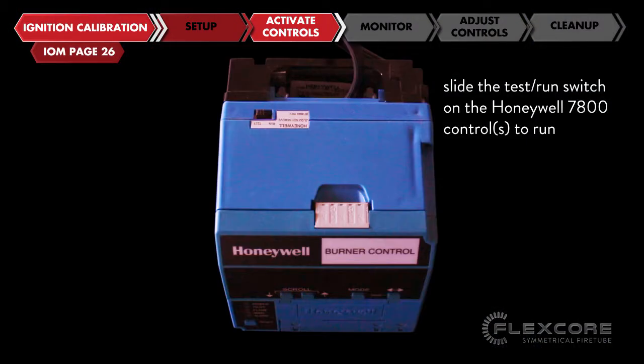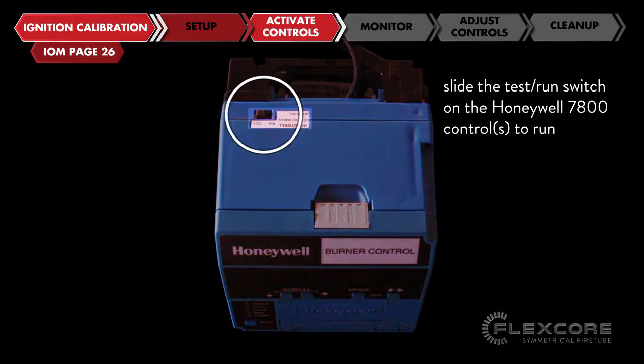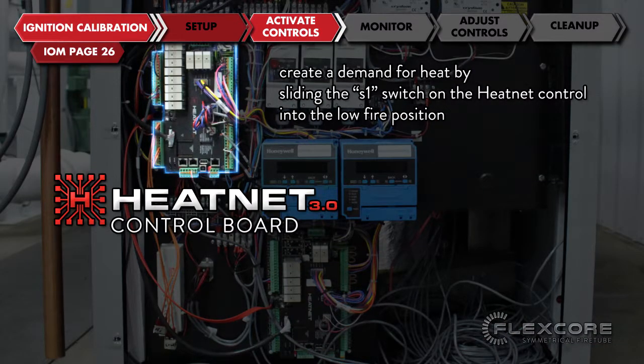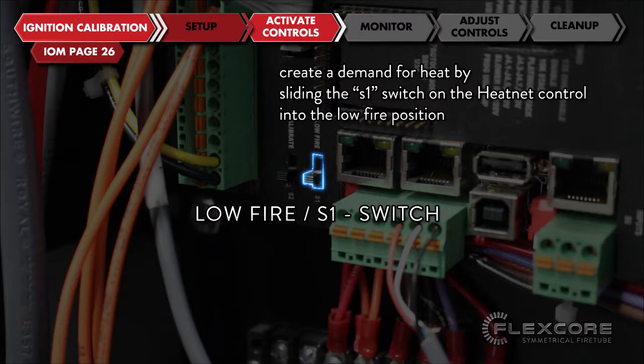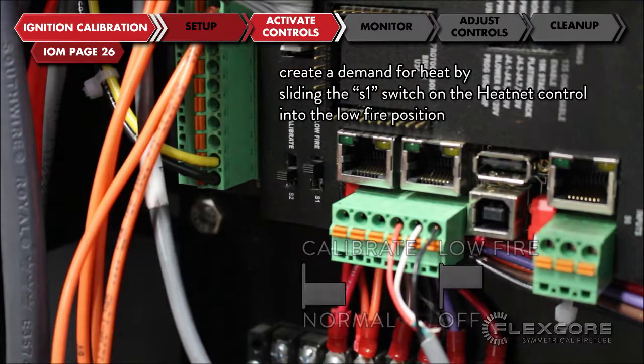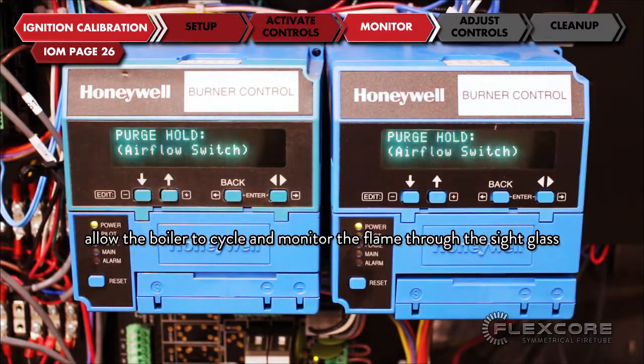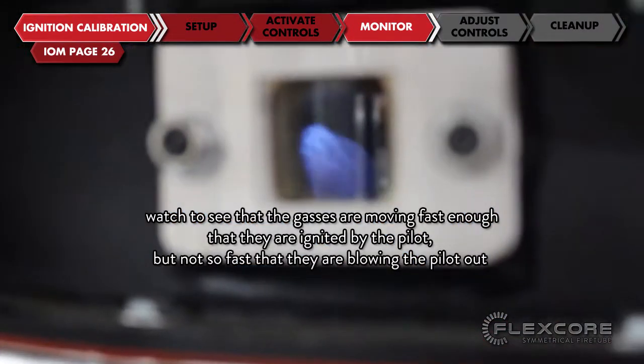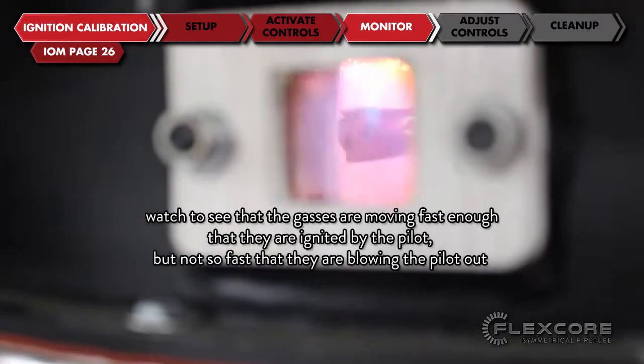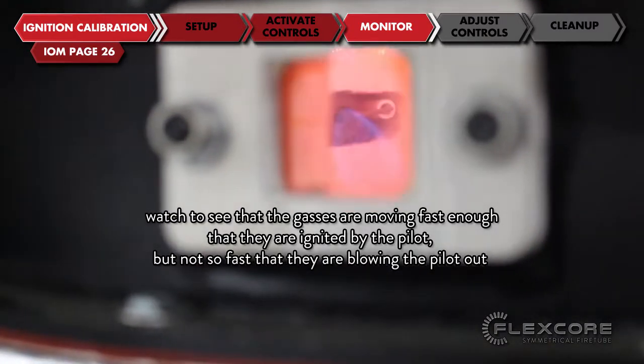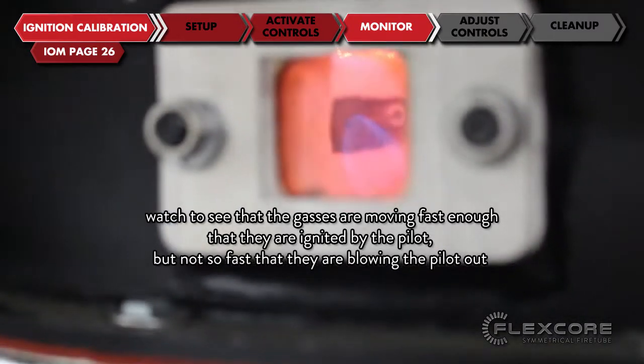Slide the test run switch on the Honeywell 7800 control or controls to run. Create a demand for heat by sliding the S1 switch on the heatnet control into the low fire position. Allow the boiler to cycle and monitor the flame through the sight glass. Watch to see that the gases are moving fast enough that they are ignited by the pilot, but not so fast that they are blowing the pilot out.